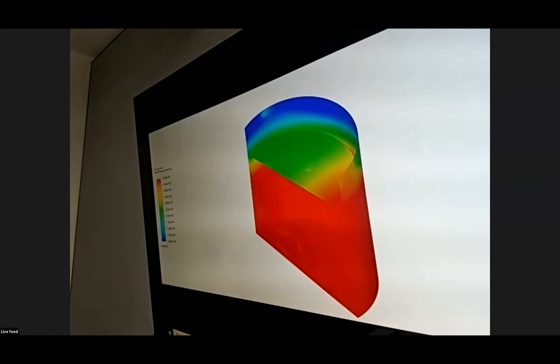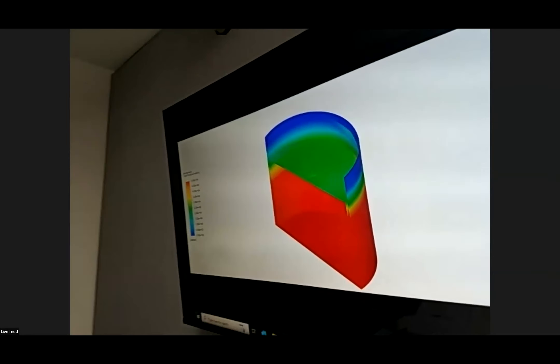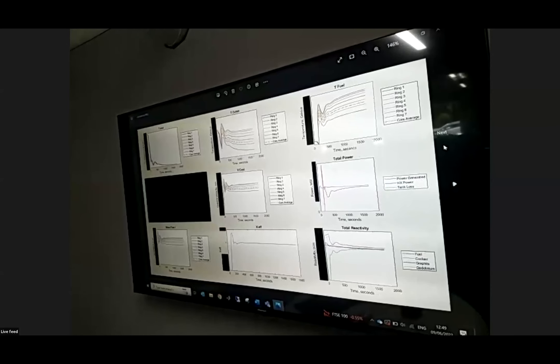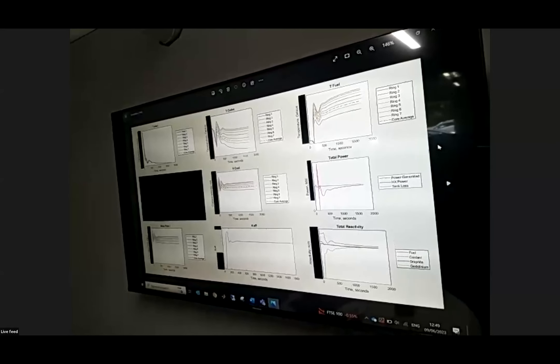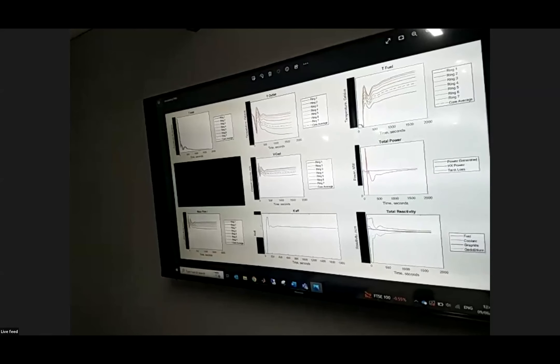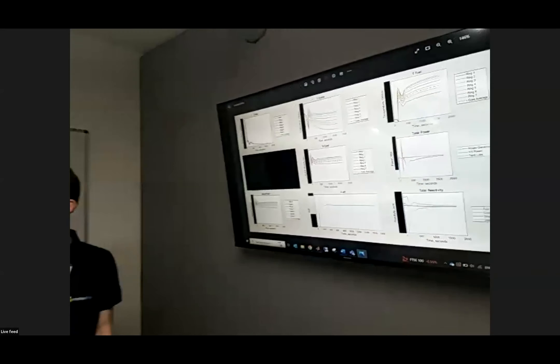As you can see, that produces quite vigorous sloshing of coolant at the top of the core. We've learned two things from this simulation: first, we need baffles on top of the core to stop the sloshing and protect equipment up there; and second, the forces on the tank and core are nothing to worry about — we can tolerate the movement of the coolant. We're still going to put baffles in because of that delicate equipment. Another unique feature is how closely coupled the thermohydraulics and neutron physics are — the hotter the reactor, the less reactive it is. We've developed an in-house coupled code where physics and thermal hydraulics feed together to investigate various transients and confirm they are acceptable.